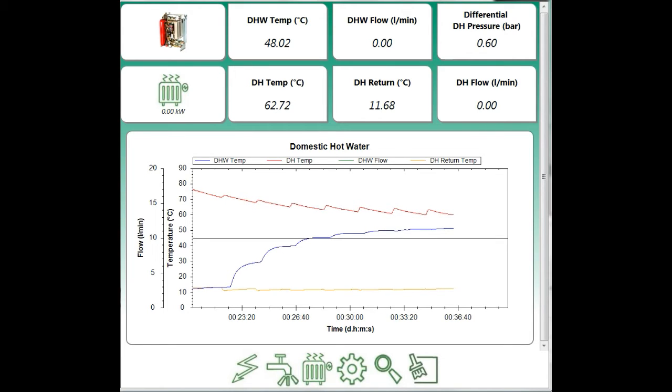The district heating return temperature is still very cold. It's still in a region of 12 degrees C. So the water that we're letting into the heat exchanger hasn't yet made it all the way through to the other side of the heat exchanger. At some point soon we should start to see a rise in the return temperature.